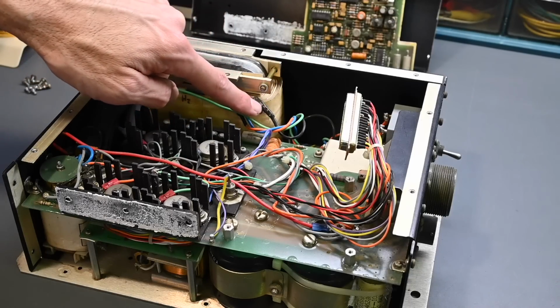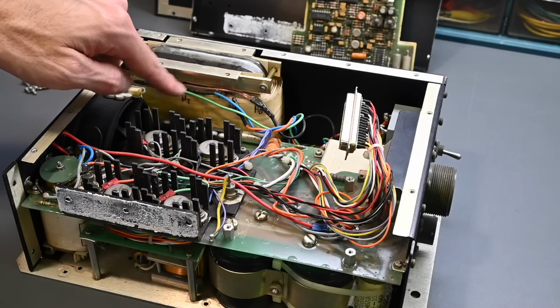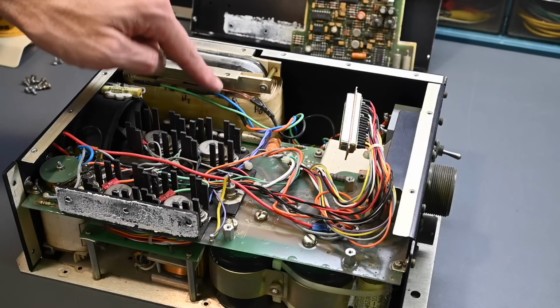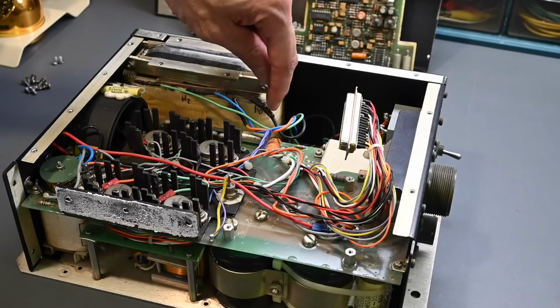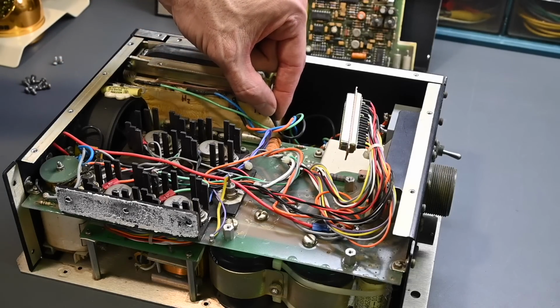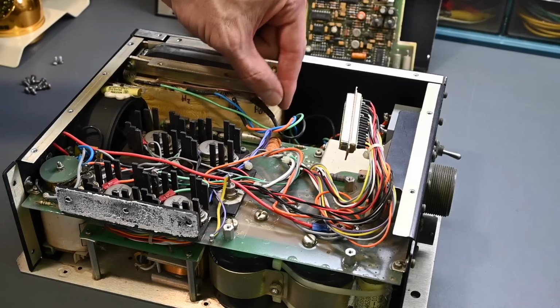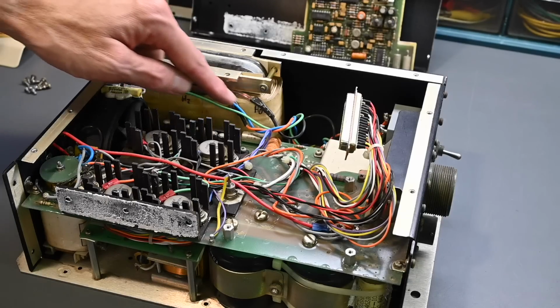You can see this black wire right here, it has the 3-phase windings, so the 3 different windings all joined back together. That's the common point that would be at the center of the Y configuration. So that's the neutral, and then these are the 3 phases right there.